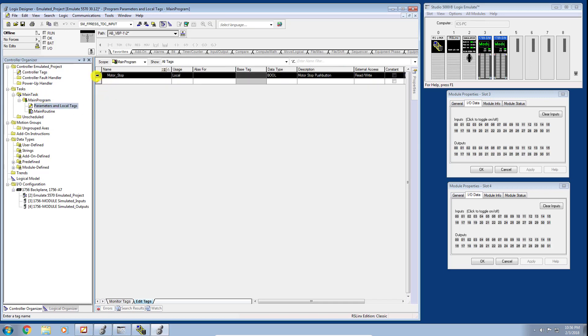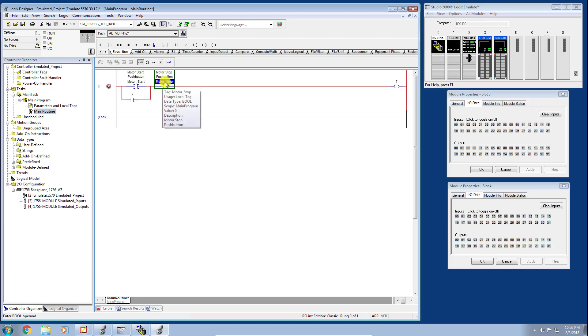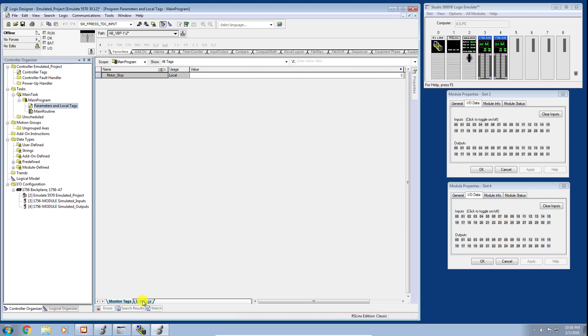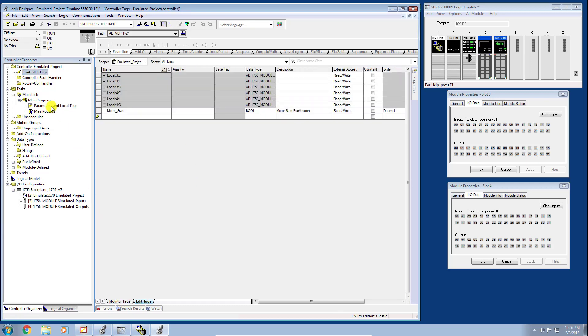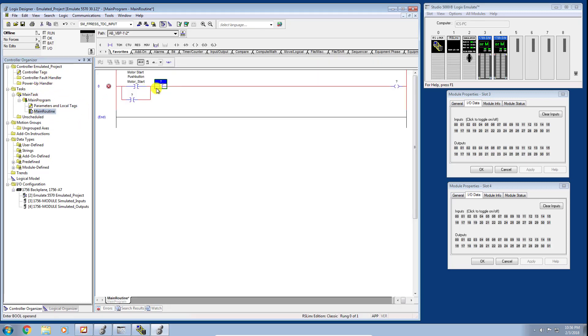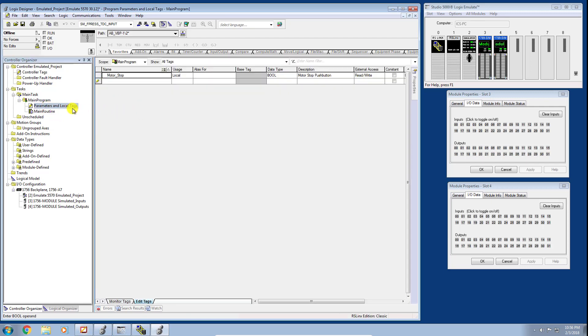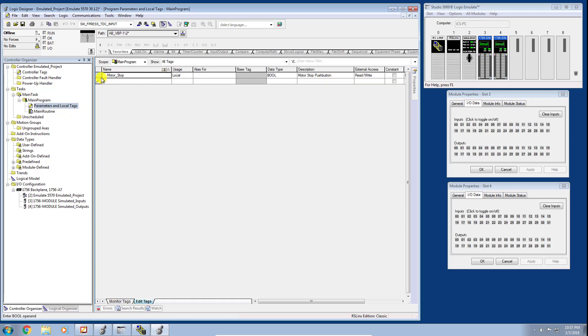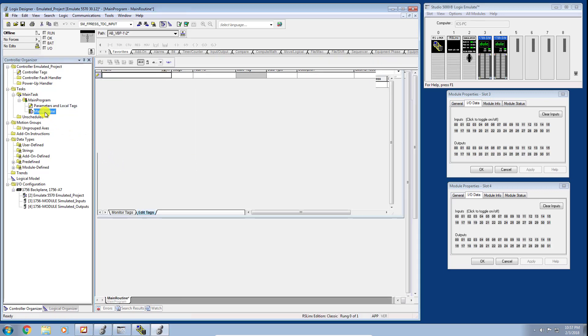I really want to drive home the scope concept because it can be confusing for newcomers. I'll go ahead and delete that tag. To delete a tag from any database, you first cannot be using that tag anywhere in your program. Once it's been completely removed from use in the Logix Designer, go to the applicable database, select the Edit Tags tab, right-click, and delete the tag.